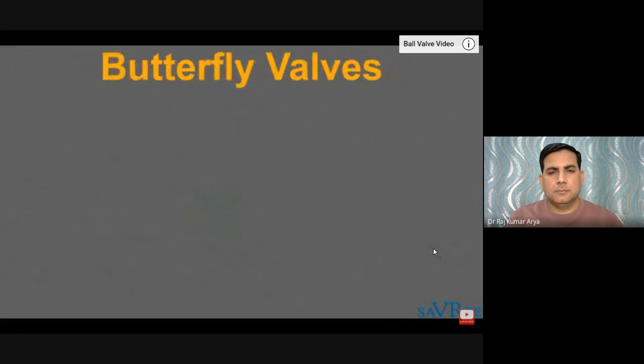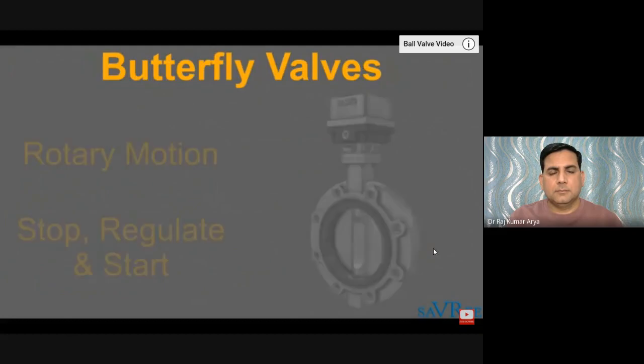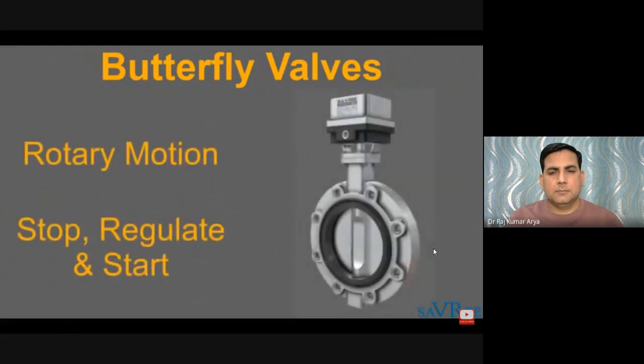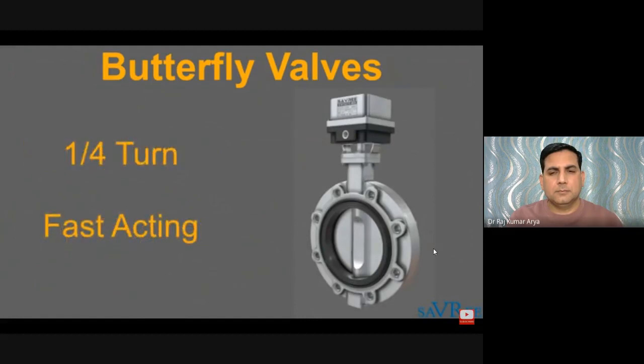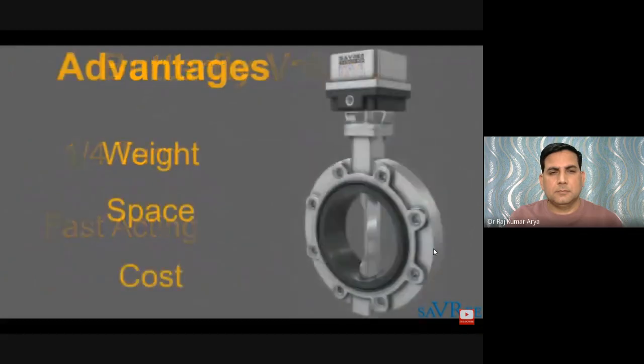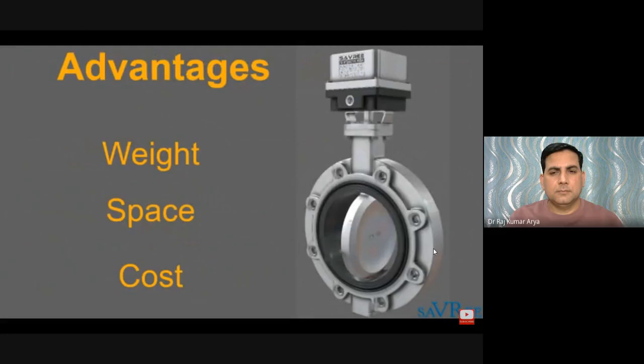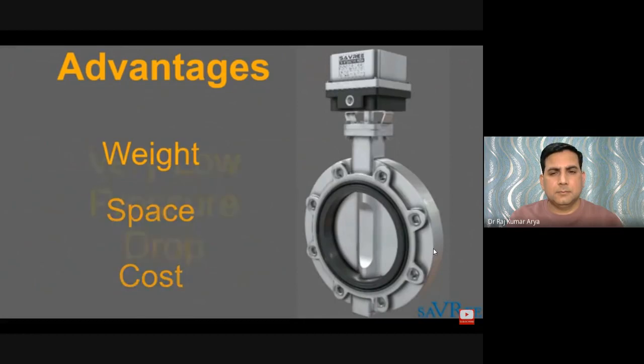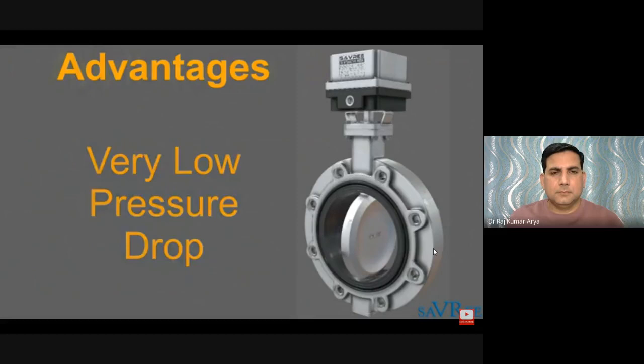A butterfly valve is a rotary motion valve used to stop, regulate, and start flow. Like all quarter-turn valves, it is fast-acting, and large butterfly valves employ planetary-type gearboxes. Butterfly valves have many advantages over gate, globe, plug, and ball-type valves, especially for larger applications, with obvious savings in weight, space, and cost. The pressure drop when fully open is low, and butterfly valves are very well suited for handling large flows of liquids or gases at relatively low pressures.